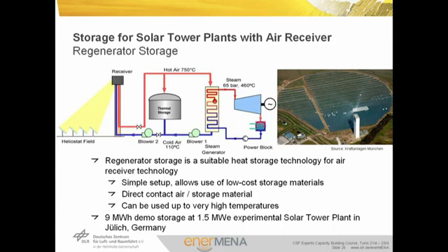Solid storage materials are also preferred for solar tower plants using air as a heat transfer medium. The regenerator storage is the suitable heat storage technology here. The setup is simple and allows the use of low-cost storage materials. Direct contact between the air and the storage material is possible and decreases the temperature difference between the working fluid and the storage material, and a very high upper temperature limit is available. A first demonstration storage with a power of 9 MW thermal has been erected at a solar tower plant in Jülich, operating with a 1.5 MW electric power cycle.